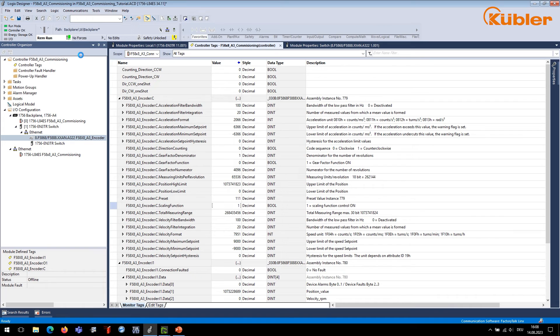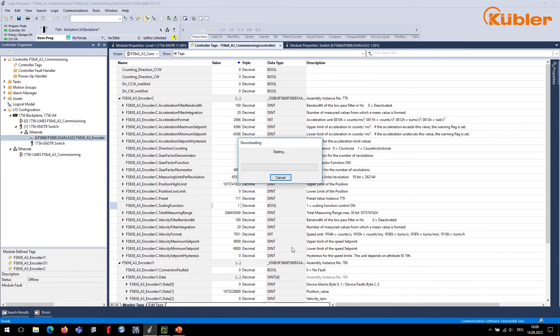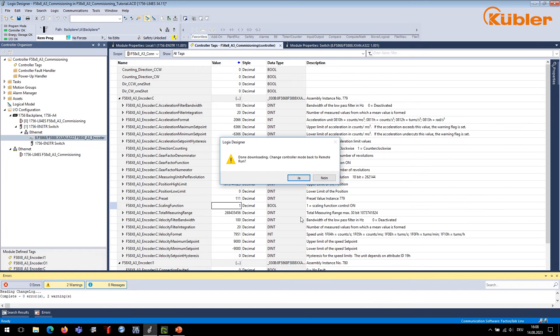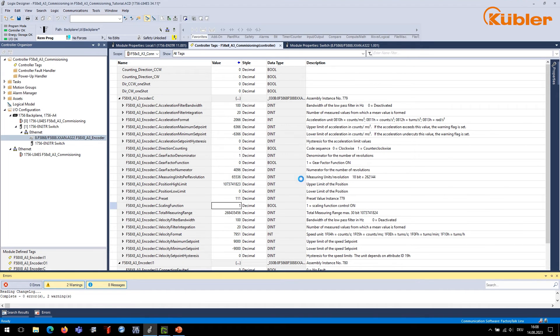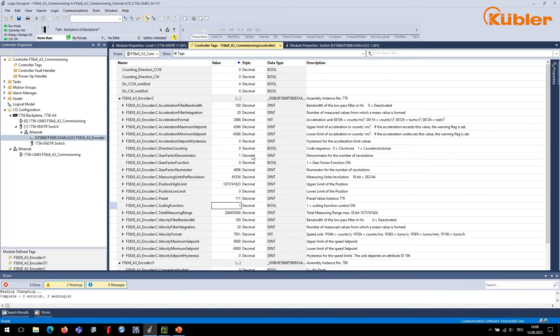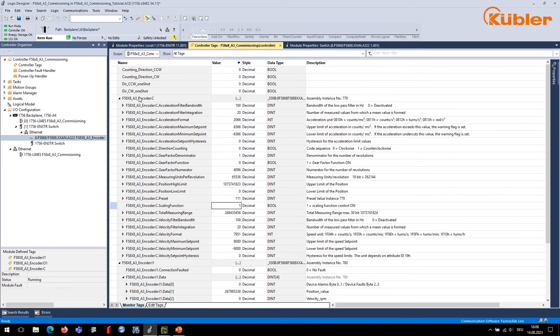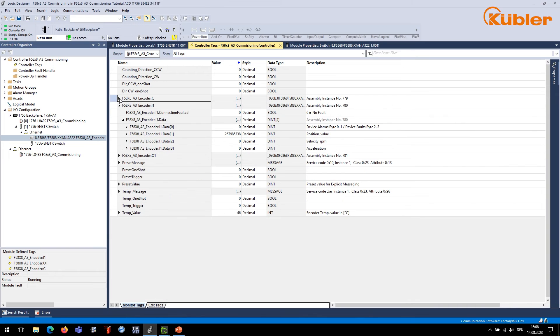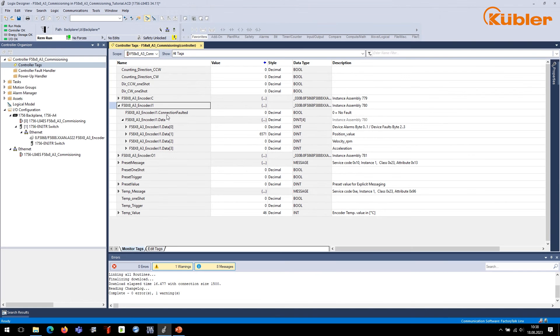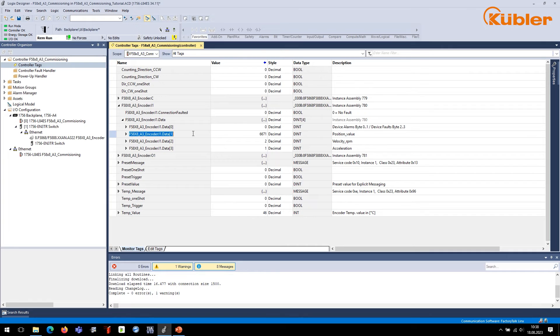Once again, we download the program to check the values with the new configuration. If the shaft is rotated around the total measuring range, we can see that the encoder scales the position based on the new scaling values.